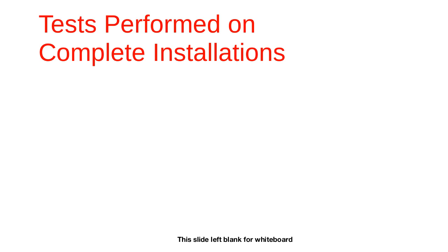And that table, the checklist table for the inspection, should have a column whereby as you check your installation, you tick as appropriate. This column should indicate the facts that should be automatically inspected by the installer. For example, how can an installer install a cable if he does not know the designer's specified cable size? As a further example, the installer should not be terminating cables if he does not know the IEE standards relating to the tightness of the connection.